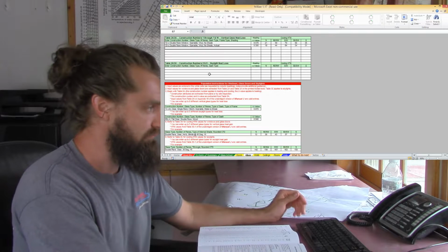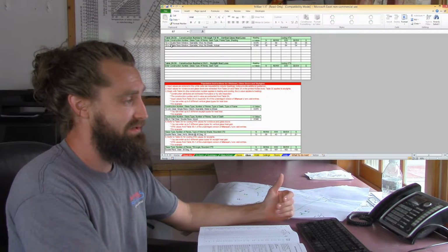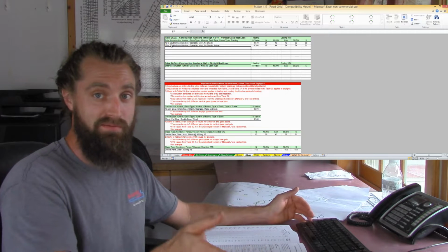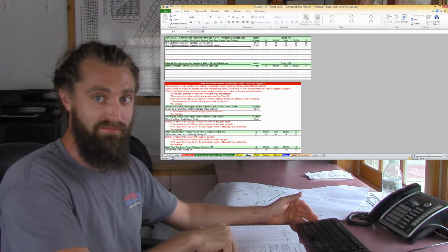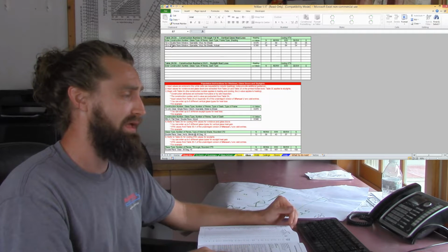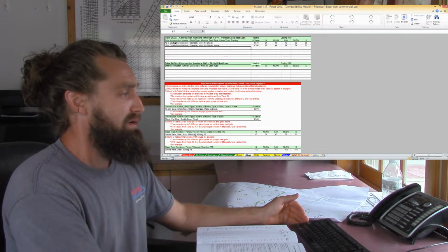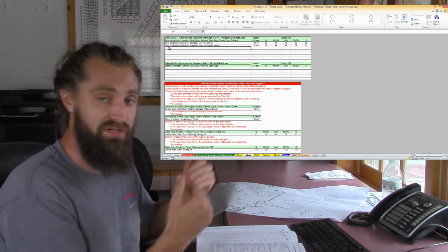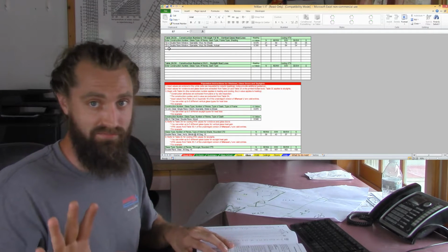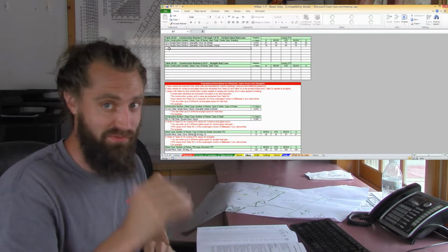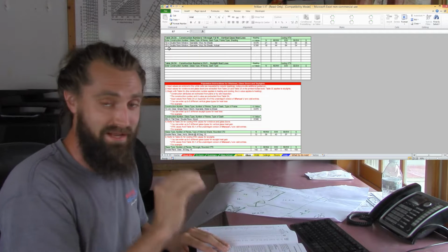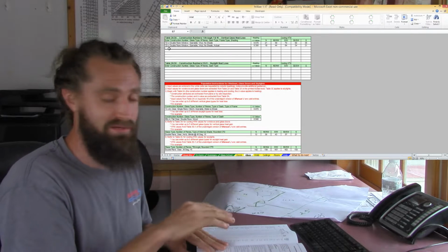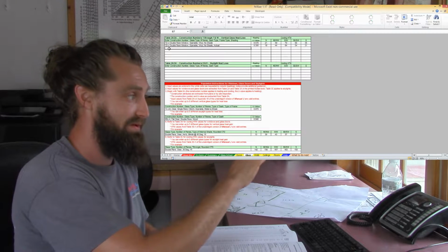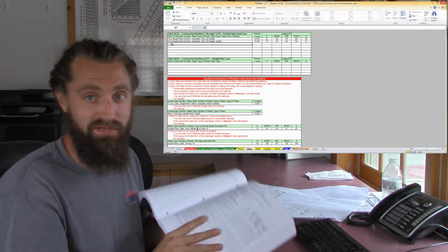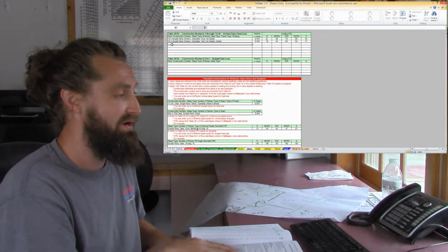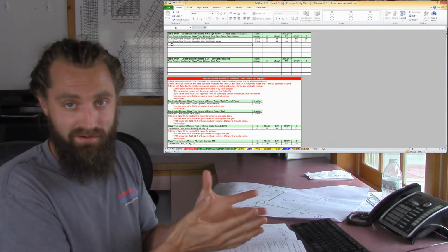Whenever I input data into this spreadsheet, some programs will automatically formulate this if it's based on the actual ACCA Manual J book, and even some ASHRAE manuals. What I put first is the actual construction code associated with whatever component I'm working with, whether it's a window, door, floor, ceiling, or wall. There's a construction code associated with that, so if anyone needs to reference what I calculated everything off of, they can go back, find that construction number, and know where we got that number.